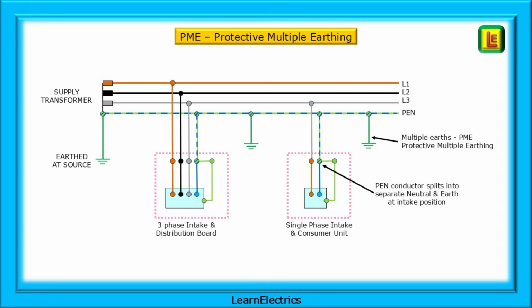This is almost the same PME drawing as page 60 in the regs book, except that I've coloured my drawing. The supply transformer is on the left with the three coloured phases L1, L2 and L3. These would ordinarily be housed in the same cable assembly as the PEN conductor. The PEN conductor is earthed at the source, the supply transformer, with additional earthing points along its route to the numerous points of use. Hopefully, in colour, you can better see the three-phase installation wiring and that of the single-phase installation.